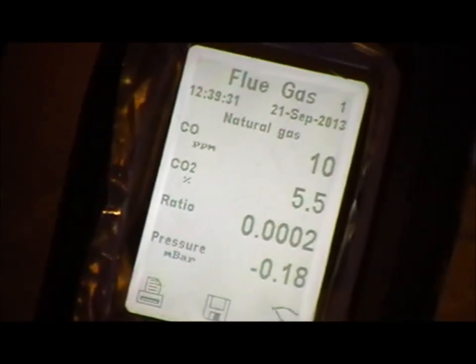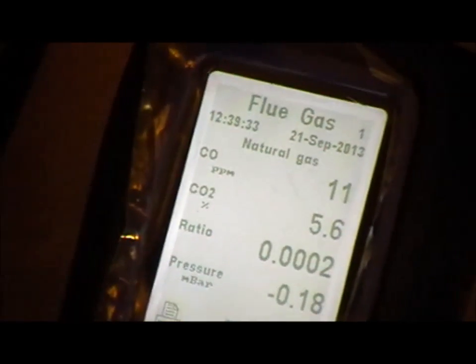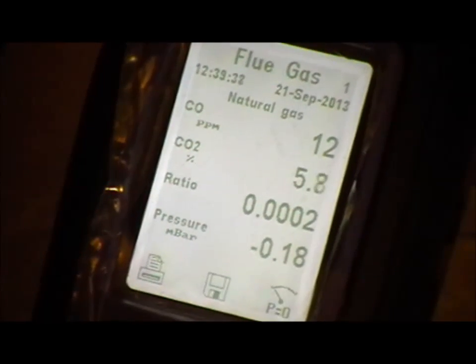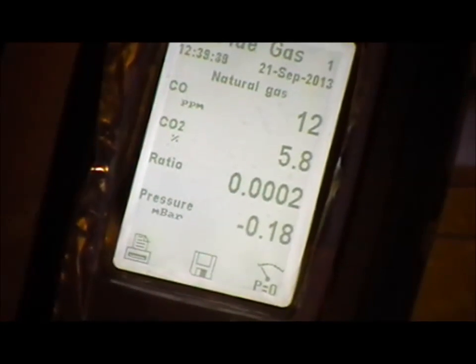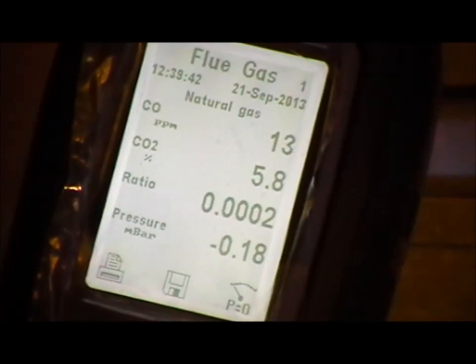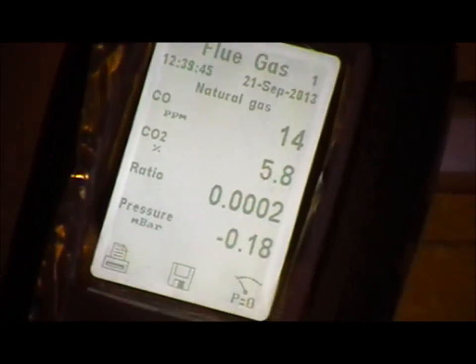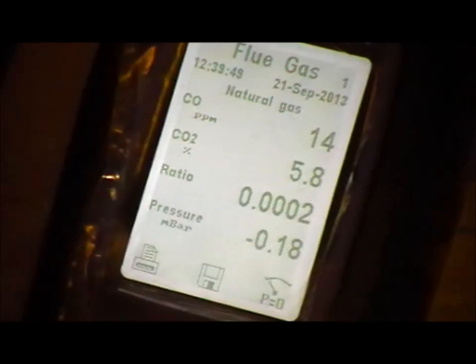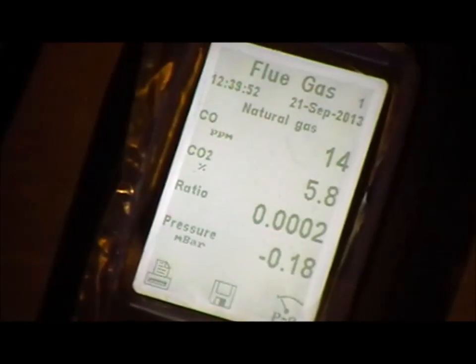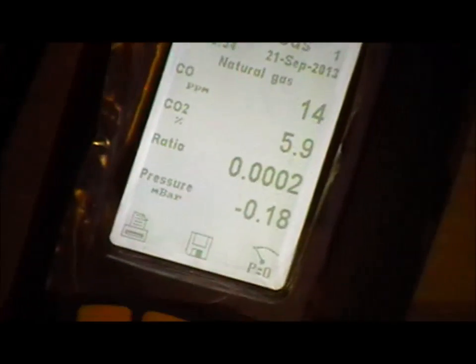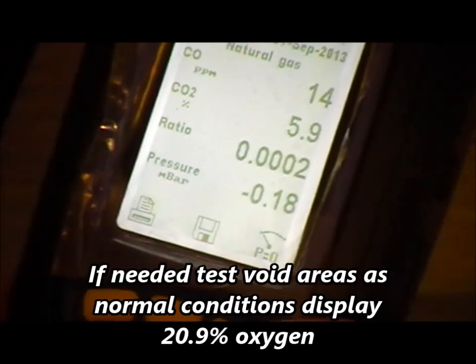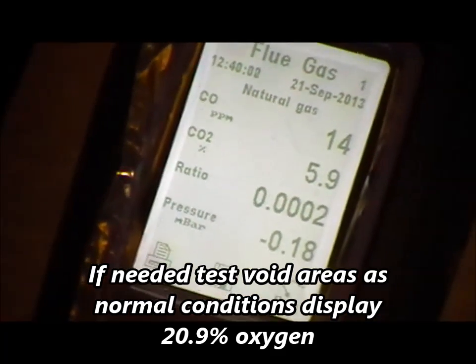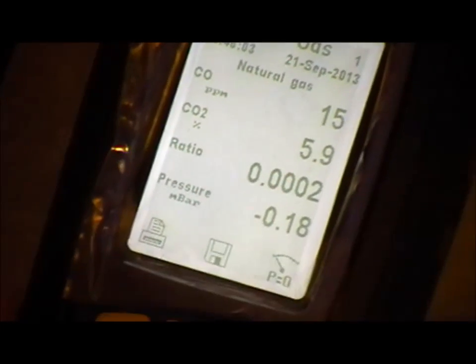This appliance doesn't have a service mode, so I've put the hot water on. You can tell from the parts per million and the carbon monoxide level that it's getting a stabilized reading. The CO parts per million is 14, which is extremely good — some appliances just have to be below 200. The ratio is 0.0002, which is absolutely superb. The CO2 is now just coming to about 6 percent.